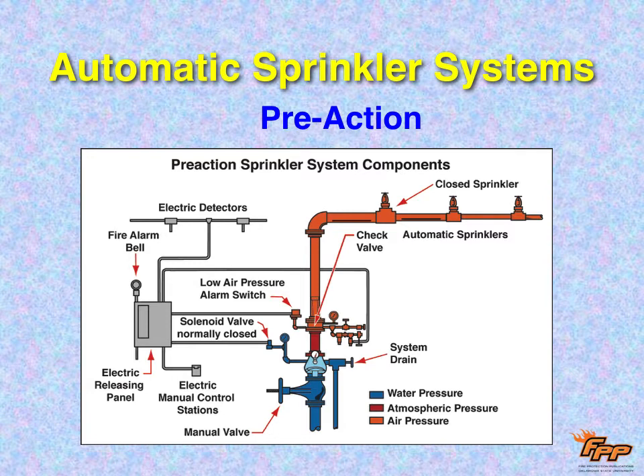So here we're going to set these detectors at a lower temperature than the sprinkler head. So if the sprinkler head is a 165, it goes off. We might set the detectors at 125 or 135 or 145. And at that temperature, it opens the valve, like the deluge system. But unlike the deluge system, it's going to just go in and hit the sprinkler heads and stop there. Now the system is like a wet pipe system. If the temperature continues to rise, wherever the temperature hits that 165 degrees, the sprinkler head is going to pop, water's going to come out, and it's already there. There's no delay.